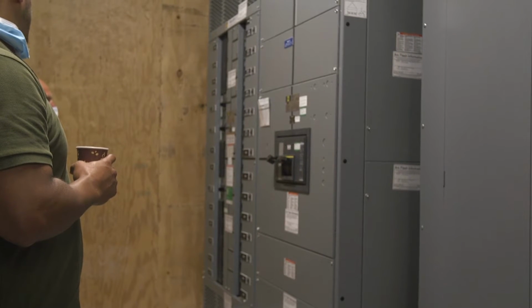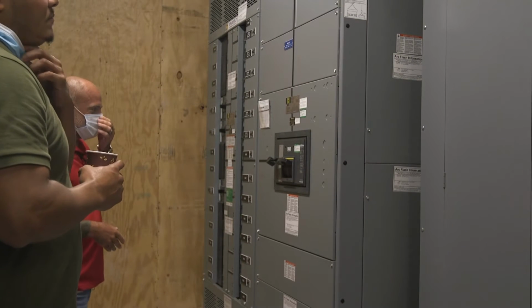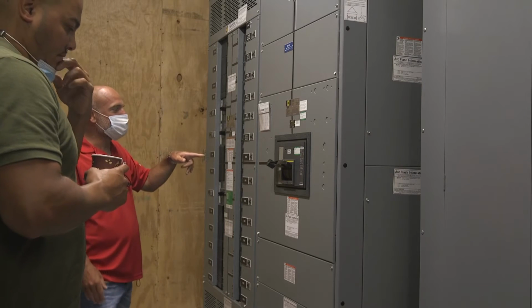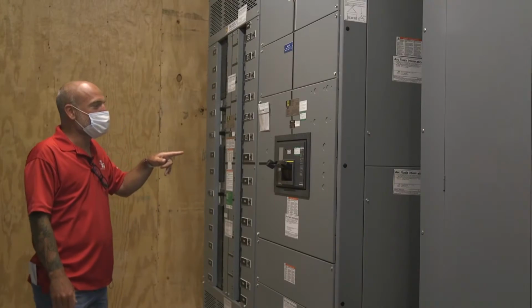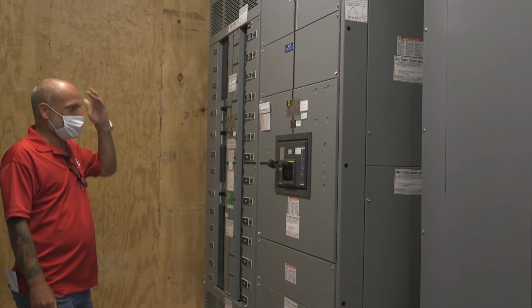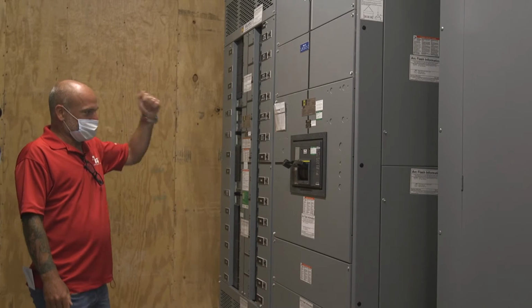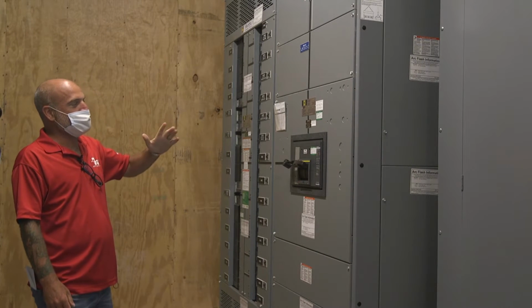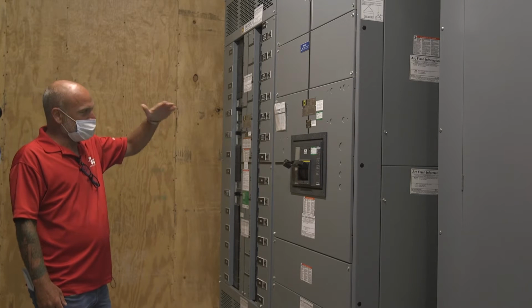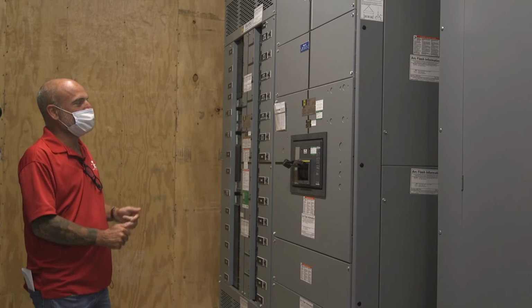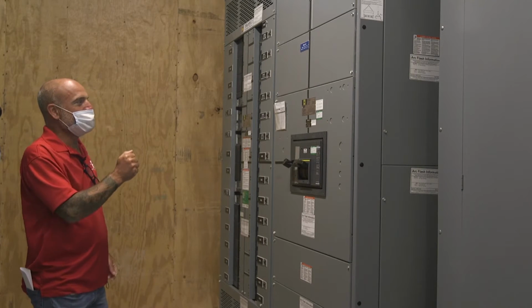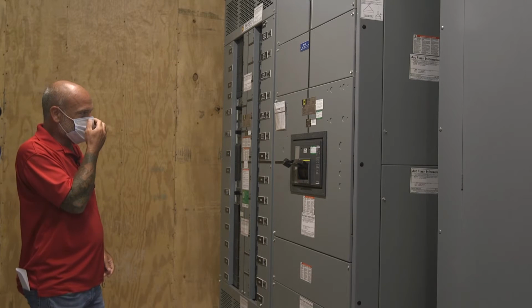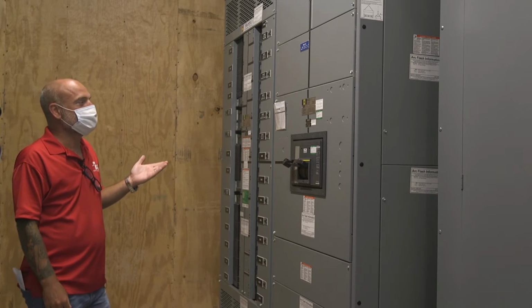All right, you have your main breaker, which is a pump action to turn it on and off. Basically very simple. Shut it down. If it ever trips, it's going to be in the mid position. From the mid position, you'd have to shut it all the way off, turn it all the way back on, and that's how you would operate that breaker.